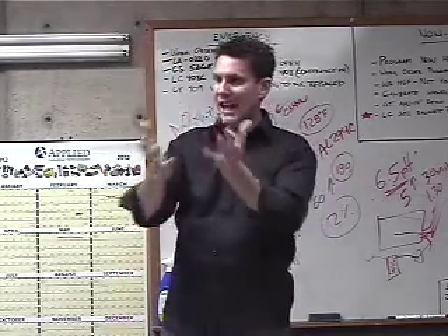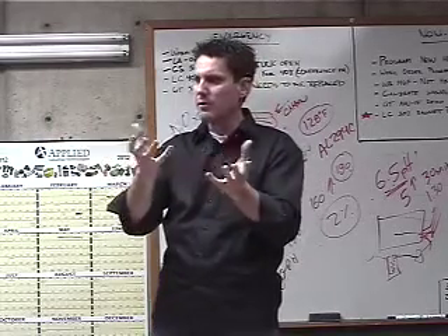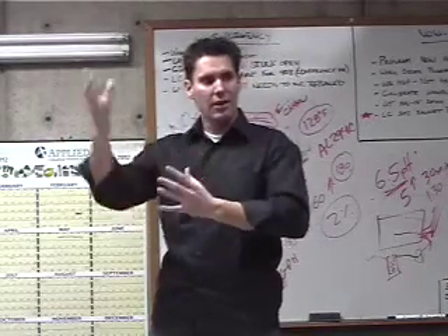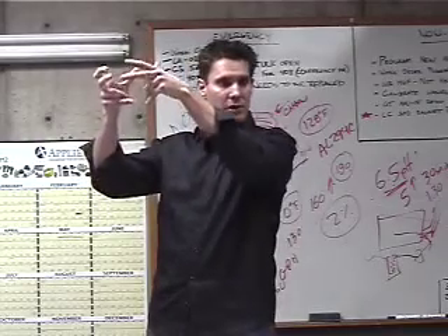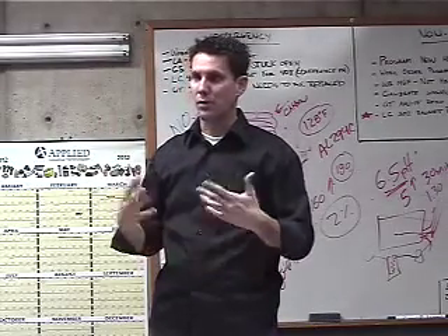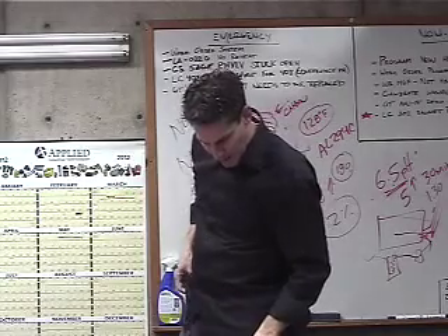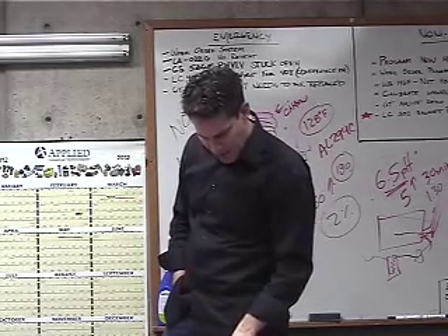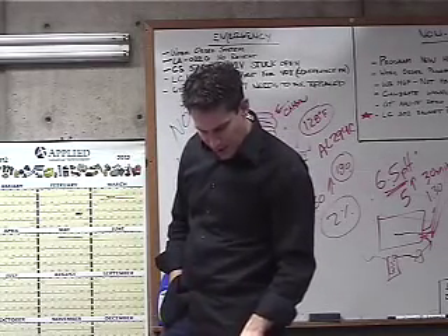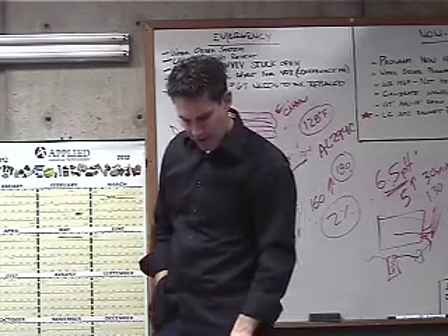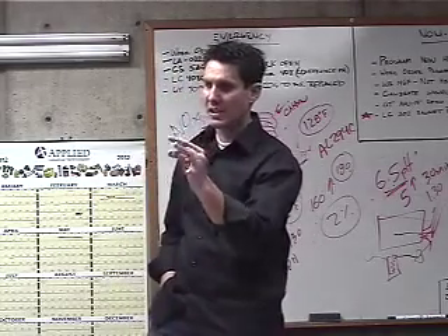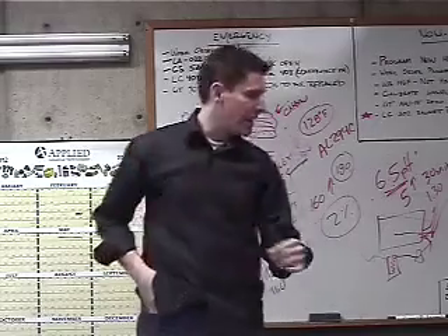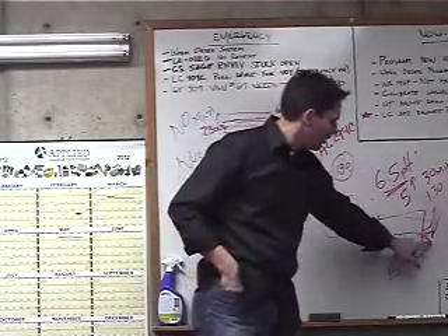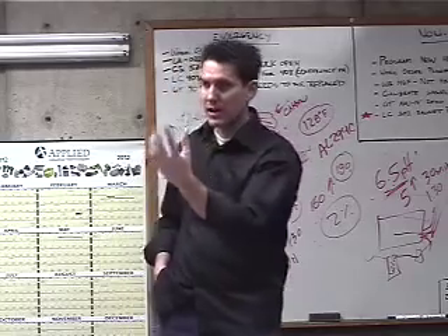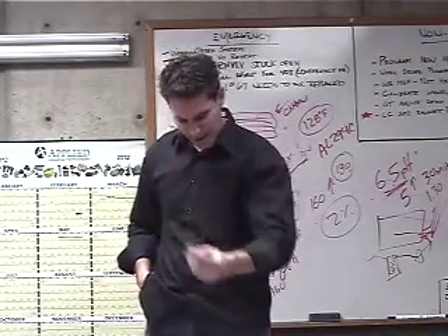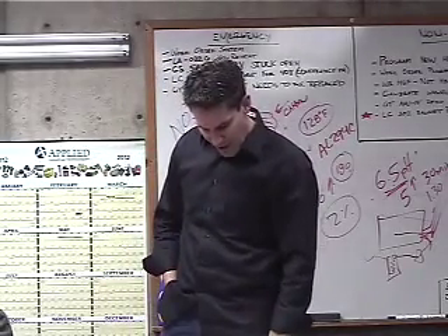Make sure there's no sagging, there's no deformation in this thing. Make sure that it's airtight. Check all of your seals, your joints. Make sure that they're sealed properly. You're not getting blow through on there. So that's what they're saying here. Check all joints, check piping for corrosion, check that the piping is clear of debris, check that the condensate drain is still functioning. Make sure that that condensate drain isn't getting plugged. So on your drain tees coming off the back of your boiler, back of your flue, make sure that those drain tees are still free and clear so that the condensate, the acid, is getting out.